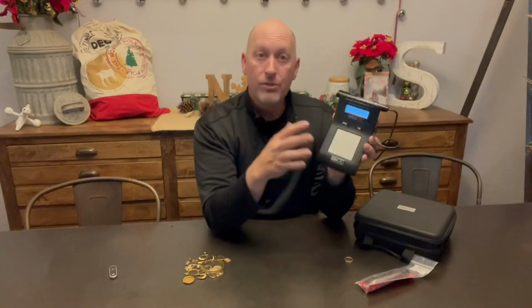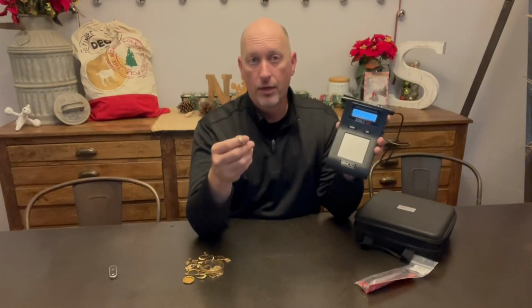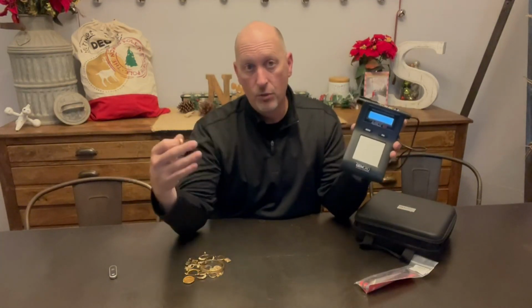So 14 karat gold's 58.3%. Well, maybe it was 58.275%, you know. It'll actually tell you that. So anyway, that's really nice. So either mode you have it in, you can calibrate this thing. If you're doing a lot of enhanced mode testing, I would definitely suggest you calibrate this in 18 karat mode. You can calibrate with an 18 karat test piece or a 14 karat gold test piece. If you calibrate with an 18 karat gold test piece, you're just ensured to be more accurate with it. 14 karat is completely sufficient for all your standard testing, especially if you're just doing quick testing.